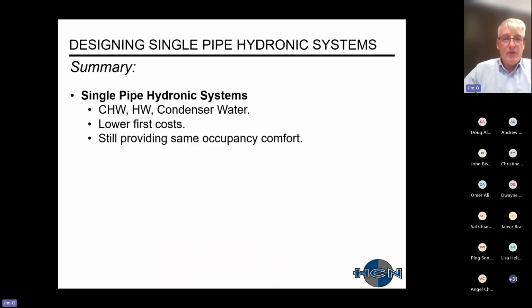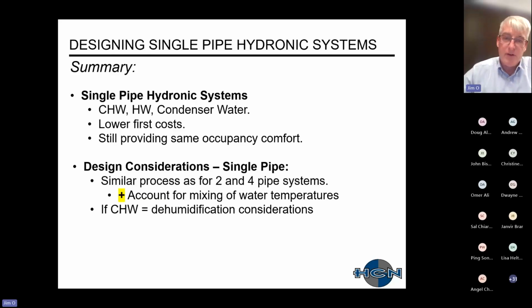All right, so coming to the end, we're at 12:53, a little bit too long with the story. Sorry about that. Anyway, we just went over single pipe hydronic systems and how they can be used on the different distribution systems. It has lower first costs because you're essentially not running that second main, but you still can provide the same occupancy comfort. With design considerations, the main thing is to realize that you have to account for the mixing of the water temperatures as you travel down the terminal units. And if chilled water, be careful of dehumidification concerns.